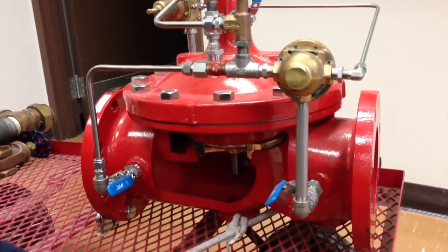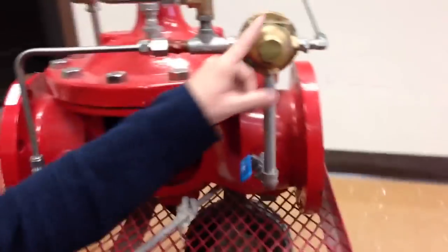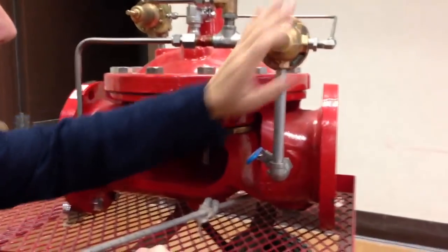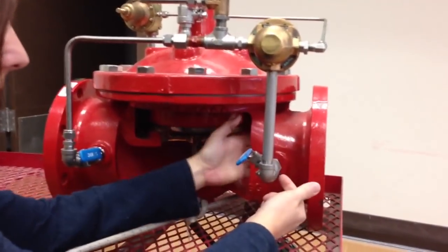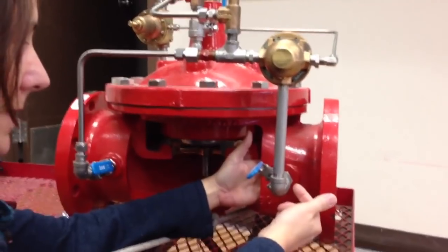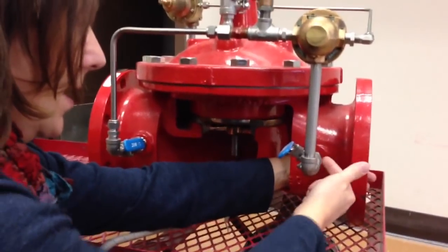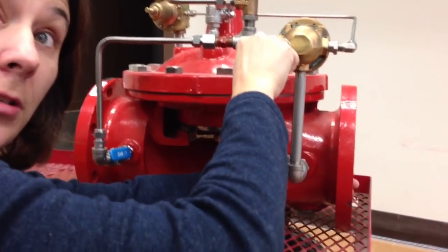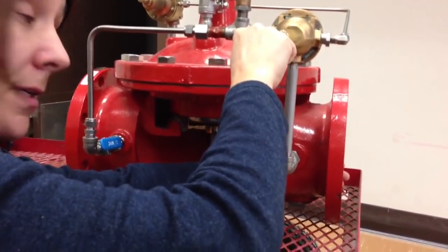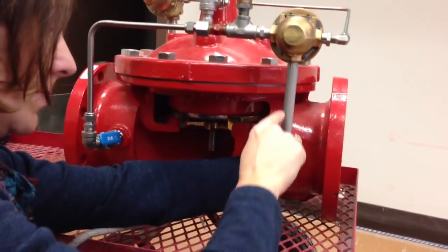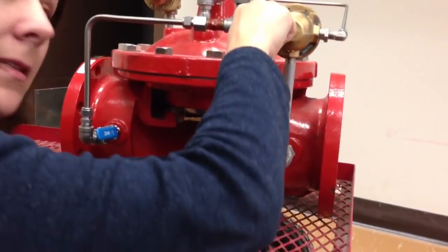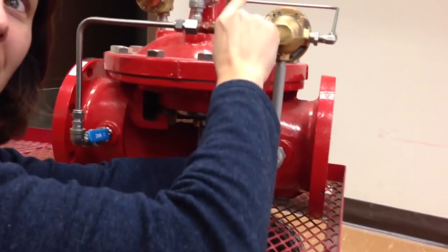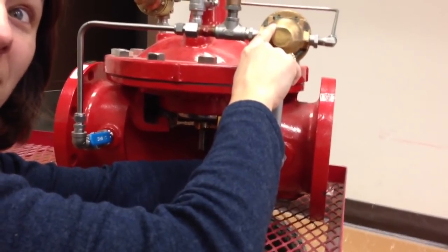So the next step of this whole process: this valve is controlled by the downstream pressure. You can see the pressure inside this main pipe connection is going to be the same pressure that's in here, and the same pressure inside the body here. So the pressure in the downstream side of this valve is transmitted through this line into the interior. It doesn't matter which way the water is going, the pressure is still going to be the same. Does that make sense?